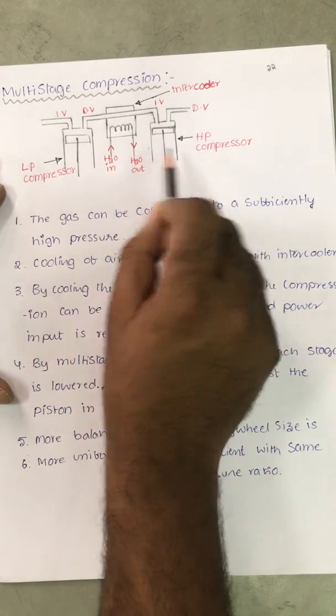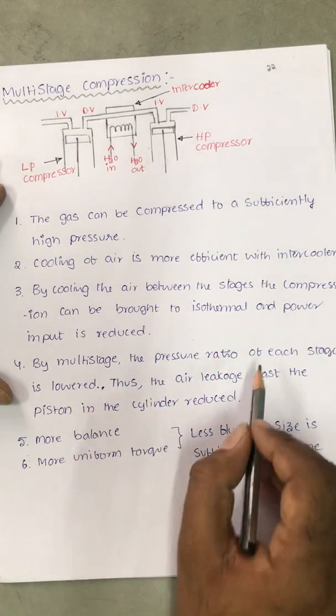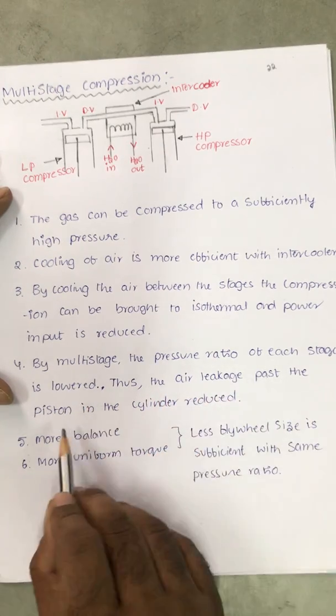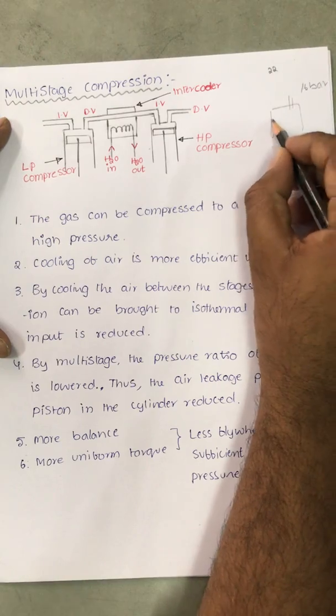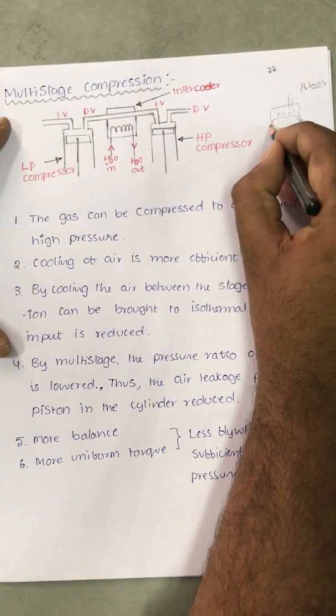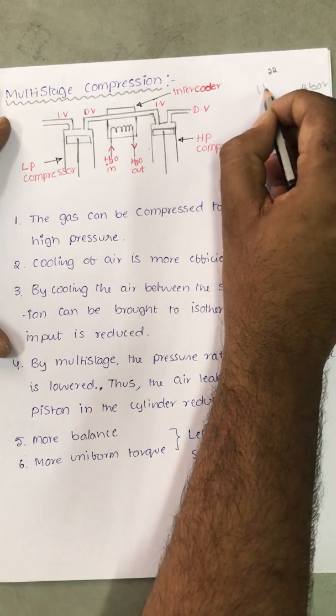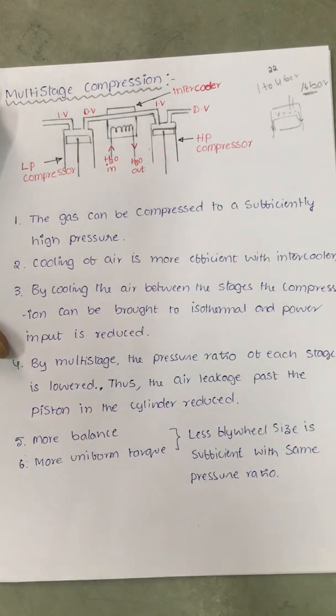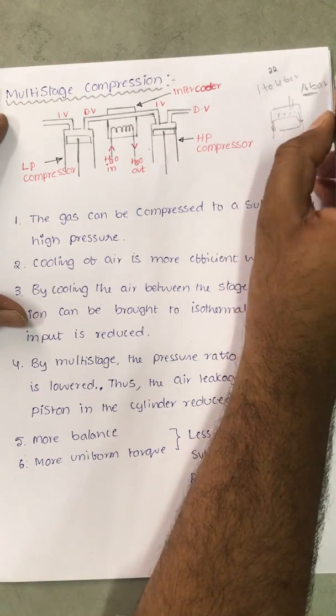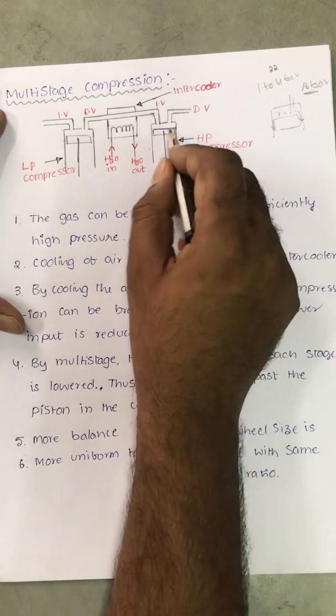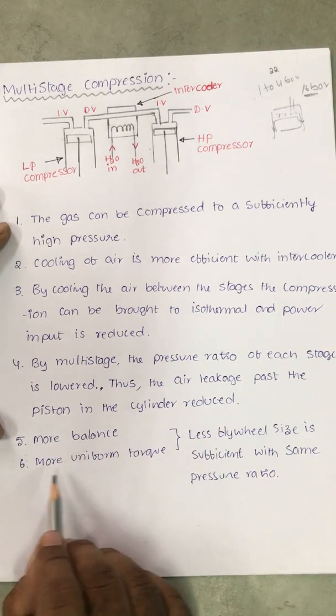With multistage compression, the pressure ratio of each stage is lowered. For example, to achieve 16 bar with a single cylinder, pressure leakage past the piston is very high. But with multi-cylinder compression — first from 1 to 4 bar, then 4 to 16 bar — the pressure ratio per stage is only 4, so the escape of gas past the piston is greatly reduced. Thus, air leakage past the piston in each cylinder is reduced.